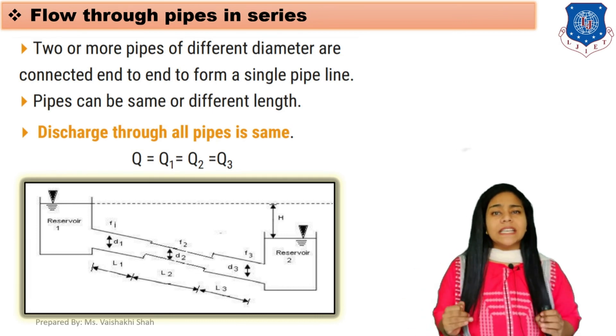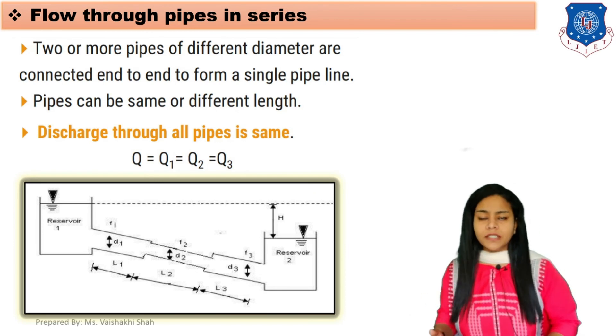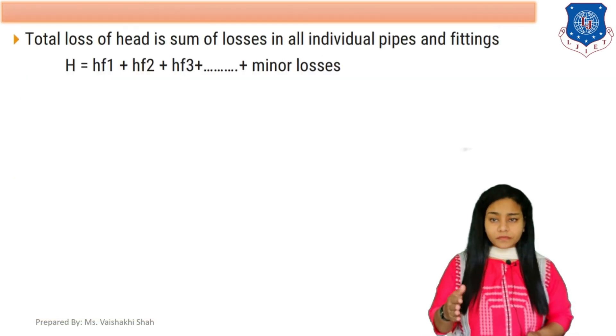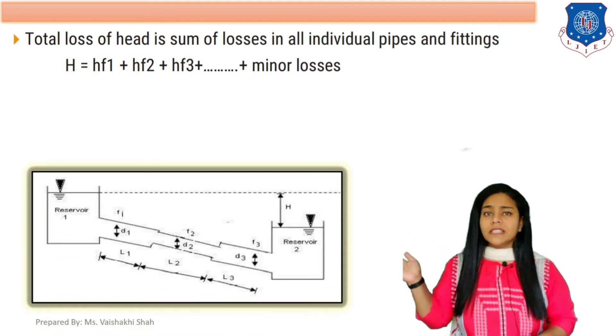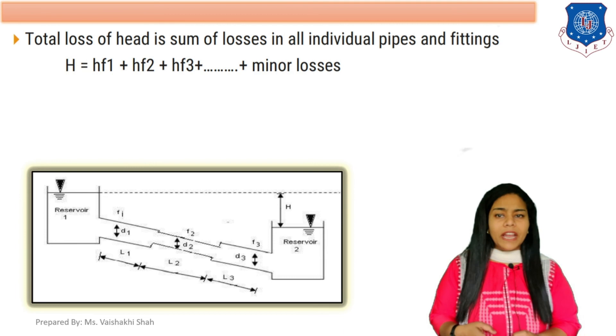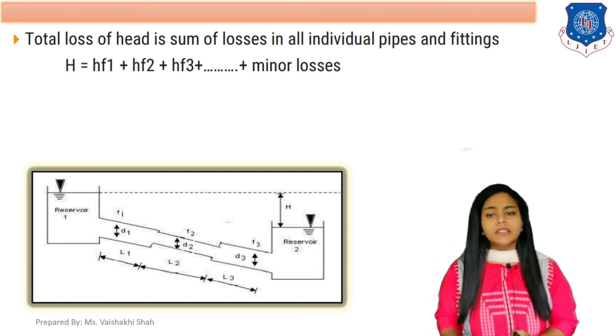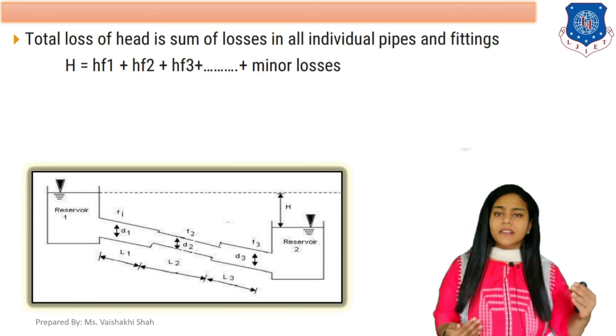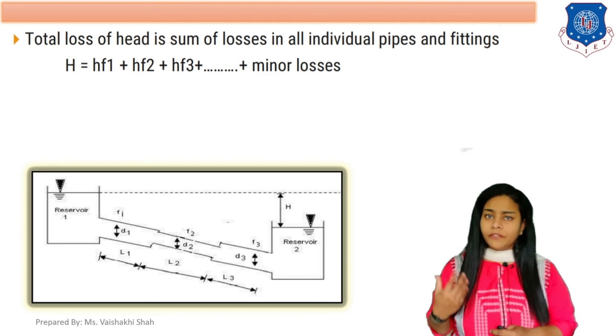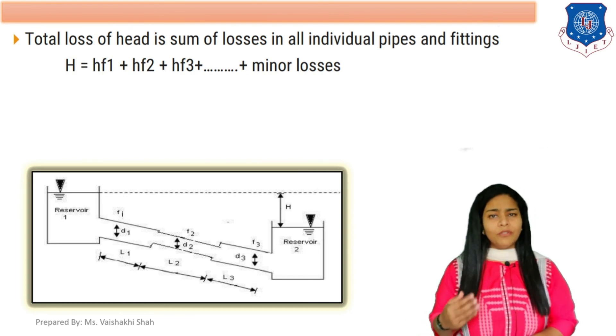When pipes are connected in series, discharge through all the pipes is the same. So Q = Q1 = Q2 = Q3, because discharge from all three pipes is equal. To find the total head loss for pipes in series, it equals the total of all head losses — exit, entry, individual pipe friction, fittings, major and minor energy losses. So H = hf1 + hf2 + hf3 plus minor losses.